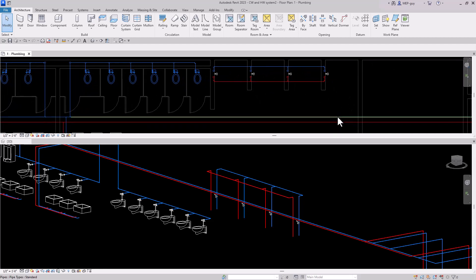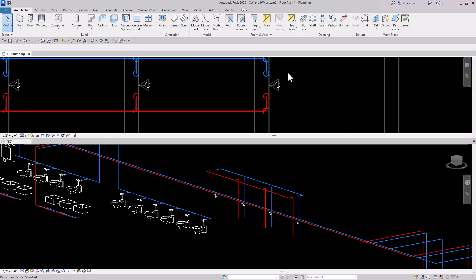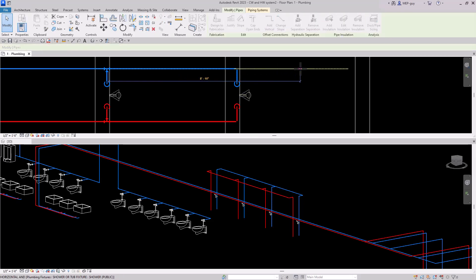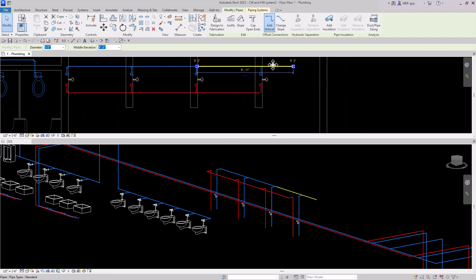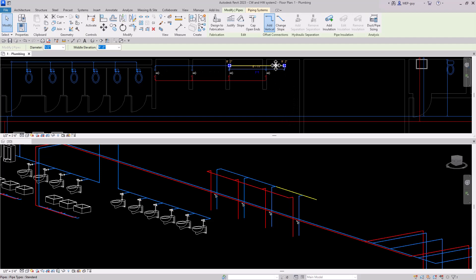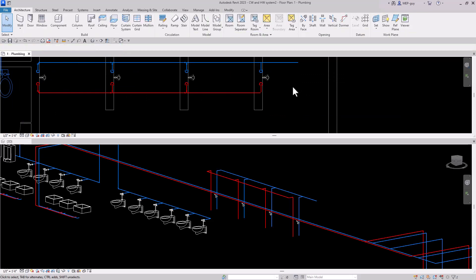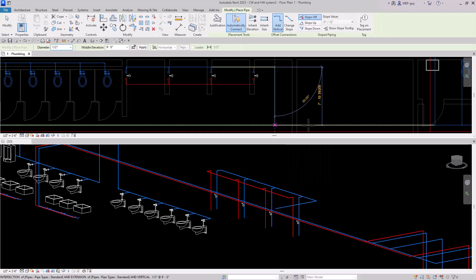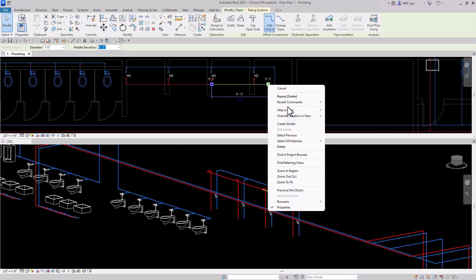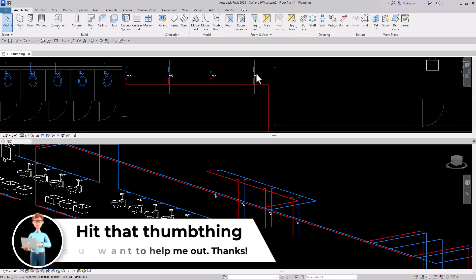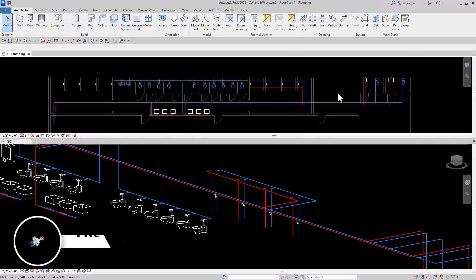We want to make our connections to the main - we can use this side or we could do this side. So let's zoom in over here. I'm just going to delete this fitting right here and this one right here, and we'll just bring this over. I realize this is at 9'2" and my main is at 9 feet, so I need to bring this main to 9 feet. So I'm going to bring this piece and this piece down to 9 feet right here, just like that. Then we'll make that connection - we can right-click, draw a pipe, and click it to that piece. Let's bring this out, right-click, use Create Similar, and make that connection right there. We'll use our Trim Extend command, select that piece of pipe, tab into this piece of pipe right here and connect it to that one. That looks pretty good, so now we have all of those showers connected up.